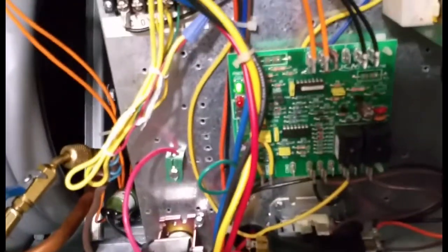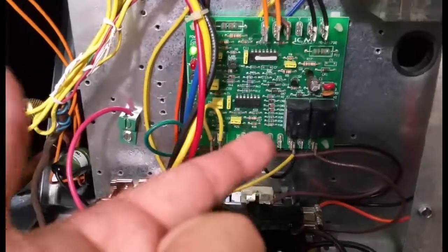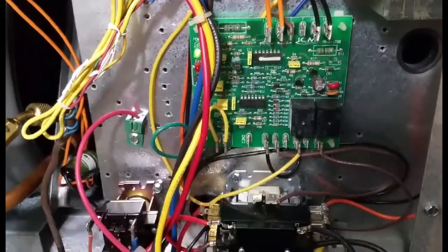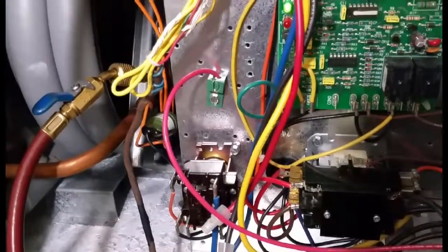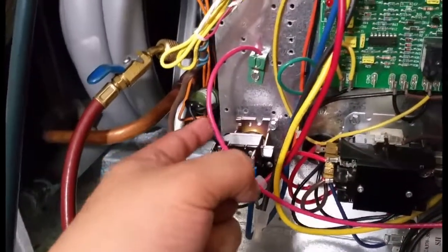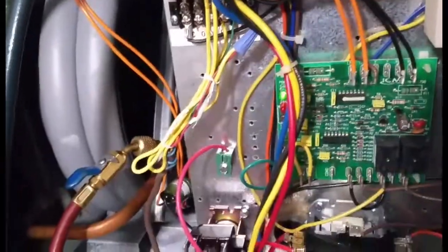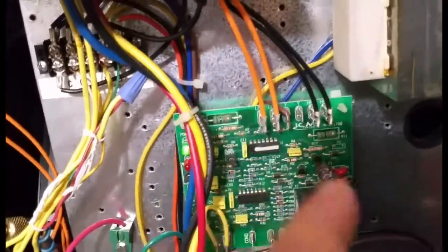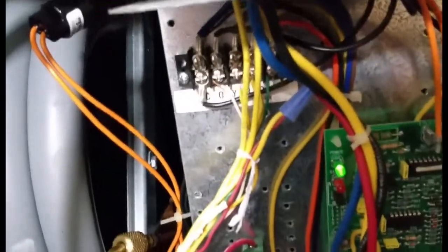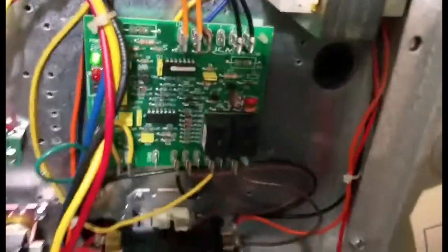A lot of technicians get intimidated when they see electronics or circuit boards and stuff, but this is just, I mean, it's not communicating. I can tell. Well, one, it's a heat pump, so it's gonna have a defrost board, but you can always tell if it's a defrost board. And this is funny, I laughed when I saw this. This is a ground. Somebody ran out of green wire. But it's really simple. You got your relays, okay, fan relay, contactor, board, and I think it's a high and low safety switches right there, your pressure switches, and then control voltage, terminal, damn it, what's that thing called? Terminal block. Again, you got a transformer.